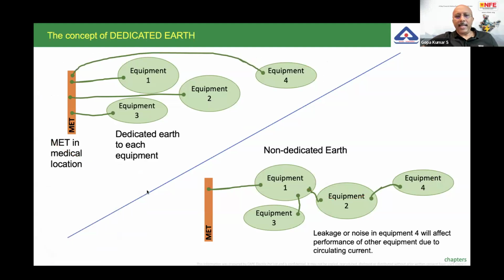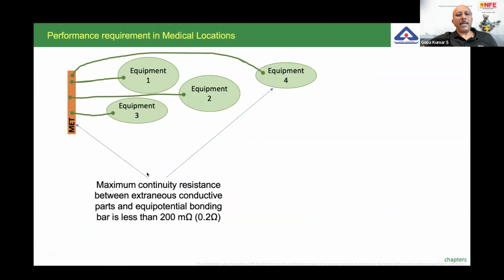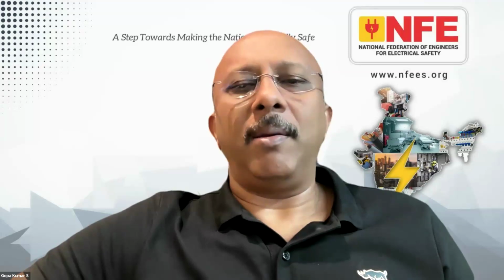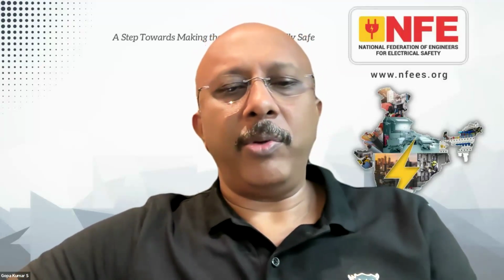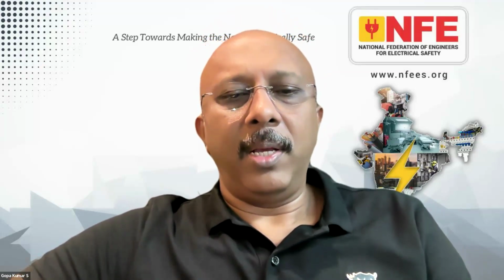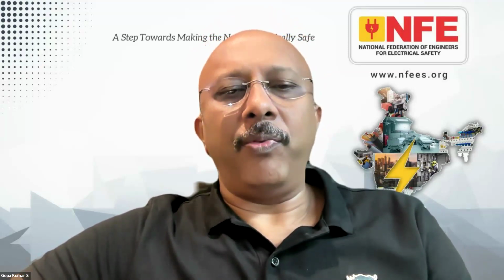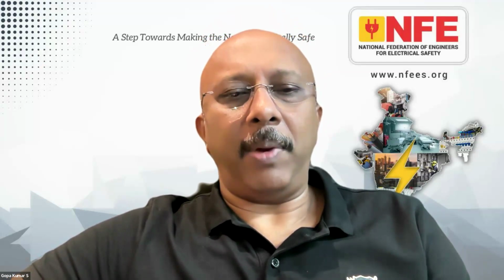Similarly, for these connections there is a maximum continuity resistance requirement. Let us say, for example, in a medical location, 200 milliohm. But of course, 200 milliohm is probably a higher value for a larger equipment. For small equipment, this value is okay. So with this in mind, the standards are very clear. The question is how we should educate, or how we should explain, to the participants.